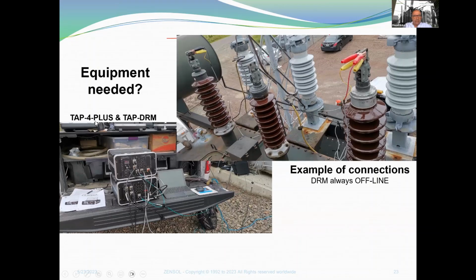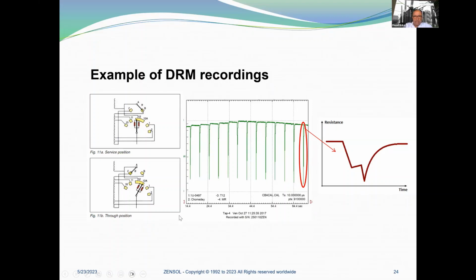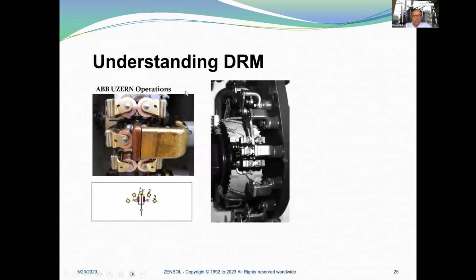So for the equipment needed here, you have what we call the Tap 4+ on the bottom, and the Tap DRM, which is an accessory that injects current on the tap changers, and of course the transformer must be offline. Here you see the kind of installation that we do. Here is an example of a DRM recording. I'm not going to talk about this curve because it's well known for the DRM curves in the industry. And here you can see with the high-speed camera the tap changer moving.